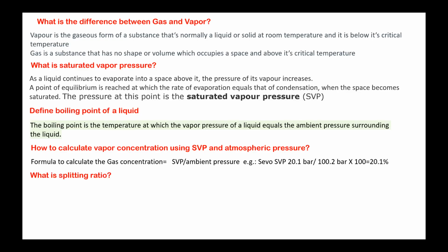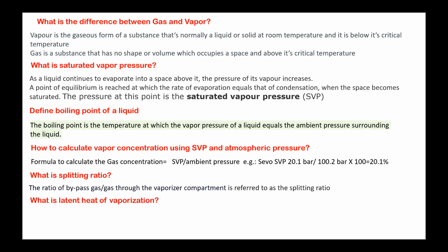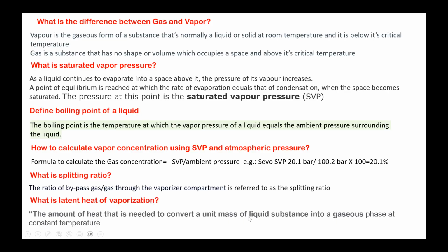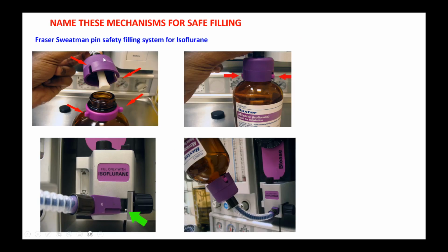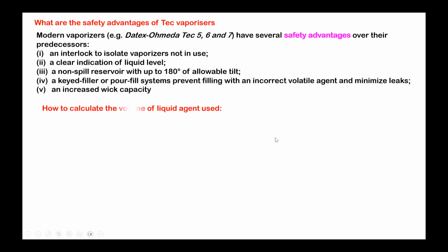And that is why we have the splitting ratio. Vaporizers deliver the correct proportion or concentration; that is the purpose of a vaporizer. What is the splitting ratio? It is the ratio between the gas flows through the bypass and the vaporizing chamber. Very good. What is the latent heat of vaporization? It is the heat required to vaporize a liquid into its gaseous form, converting the mass of liquid into the gaseous phase. And for mechanisms of safe filling, there is the Fraser-Sweatman fitting, which we use for isoflurane bottles. So just quickly go through all that.